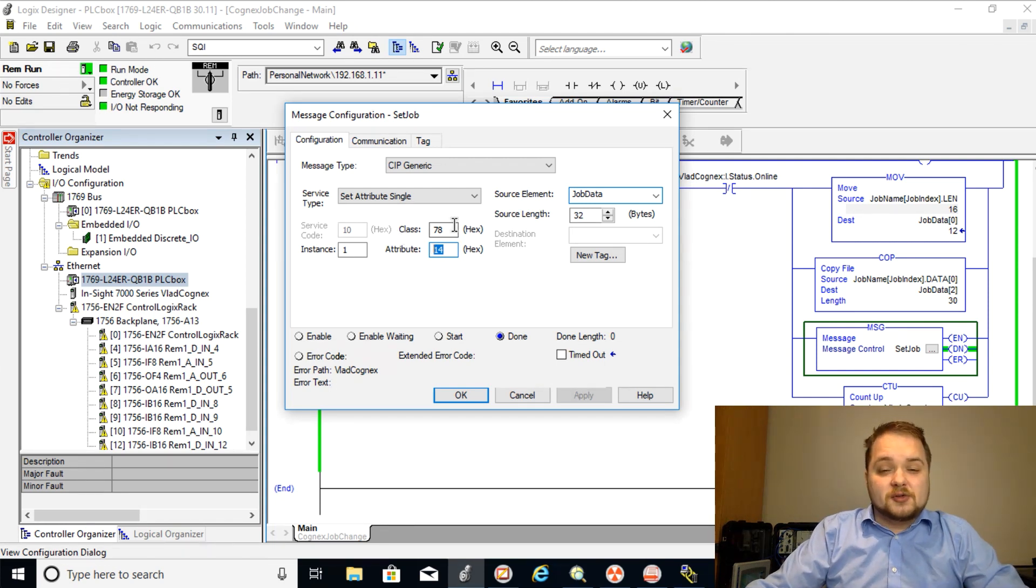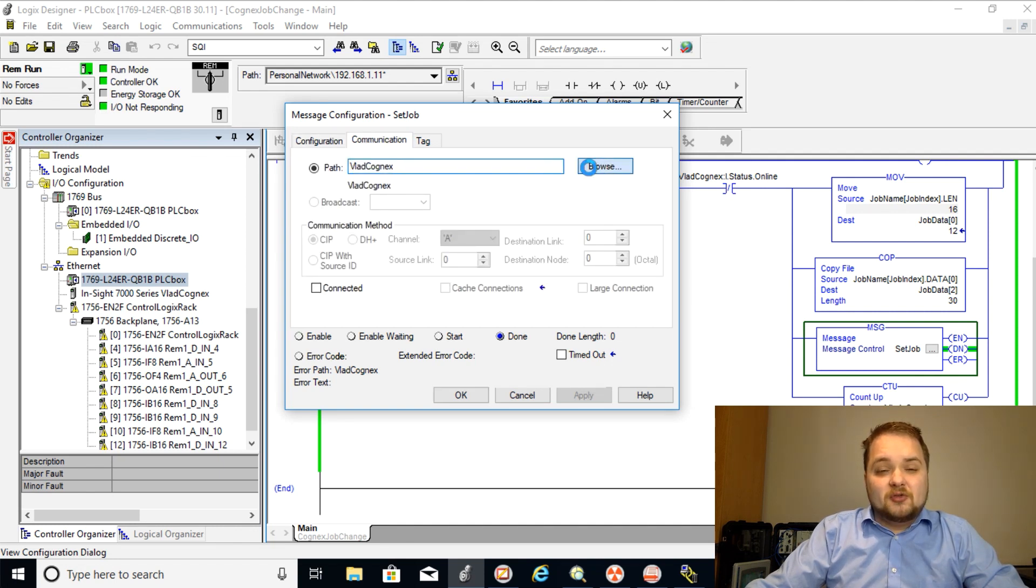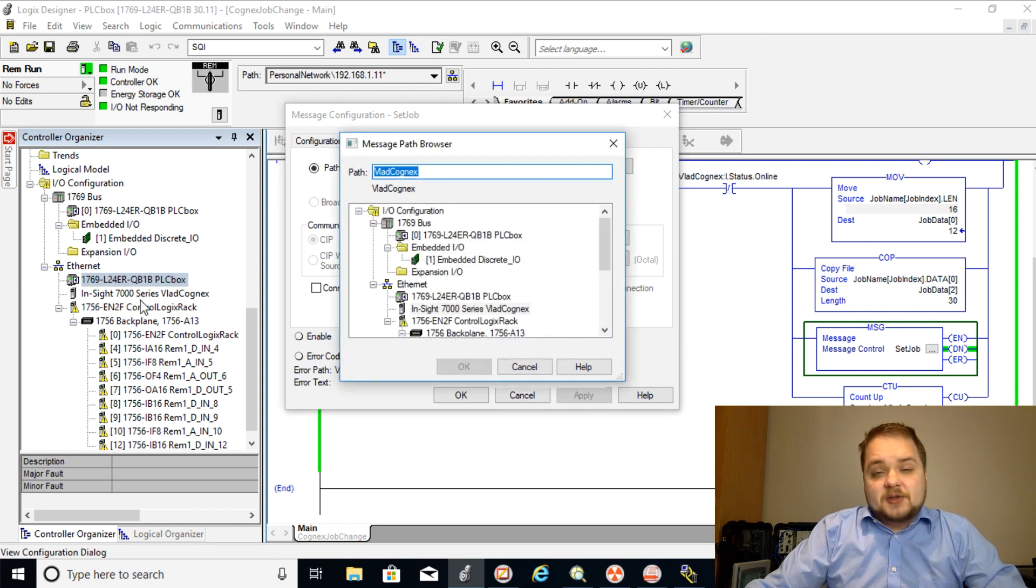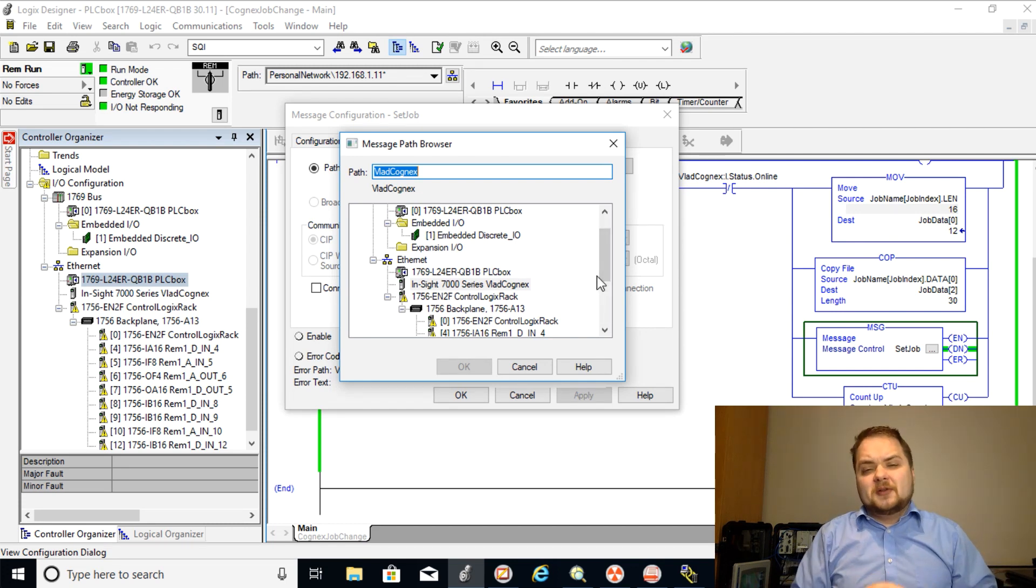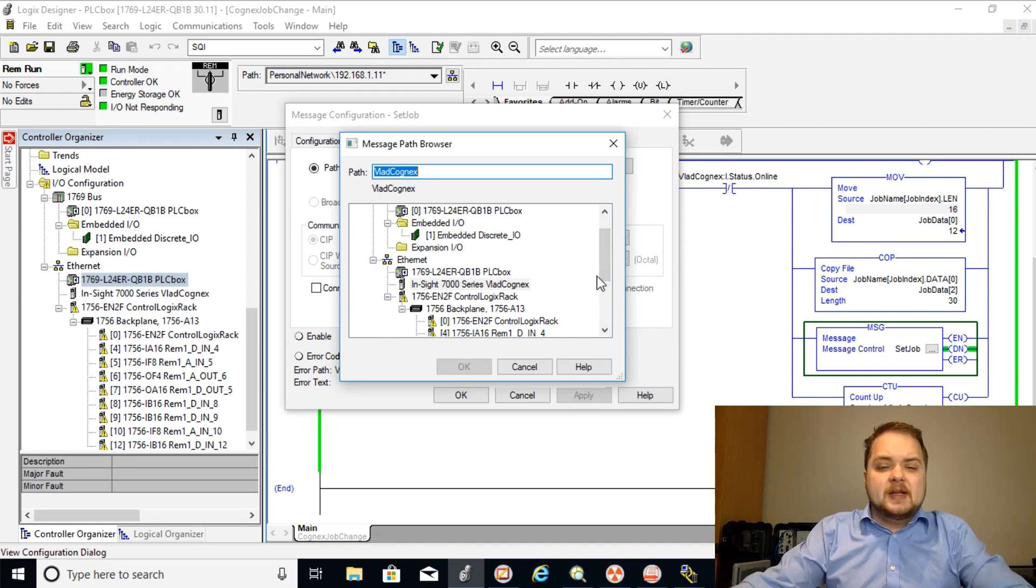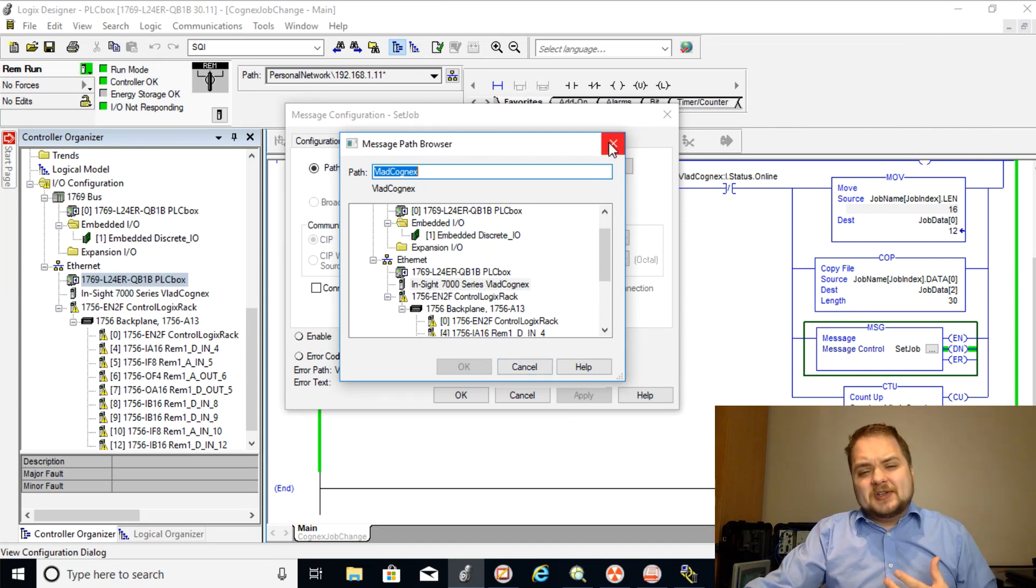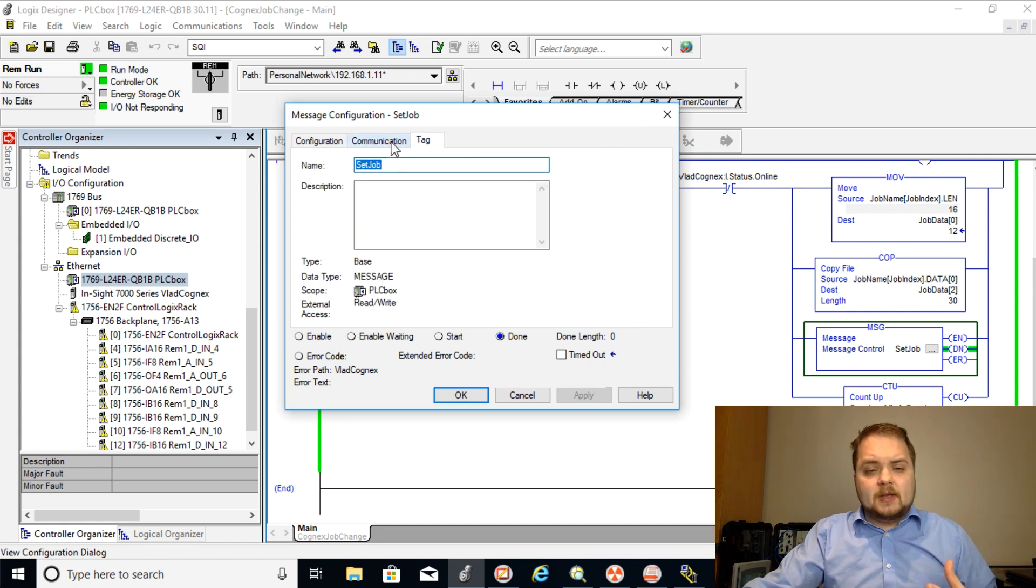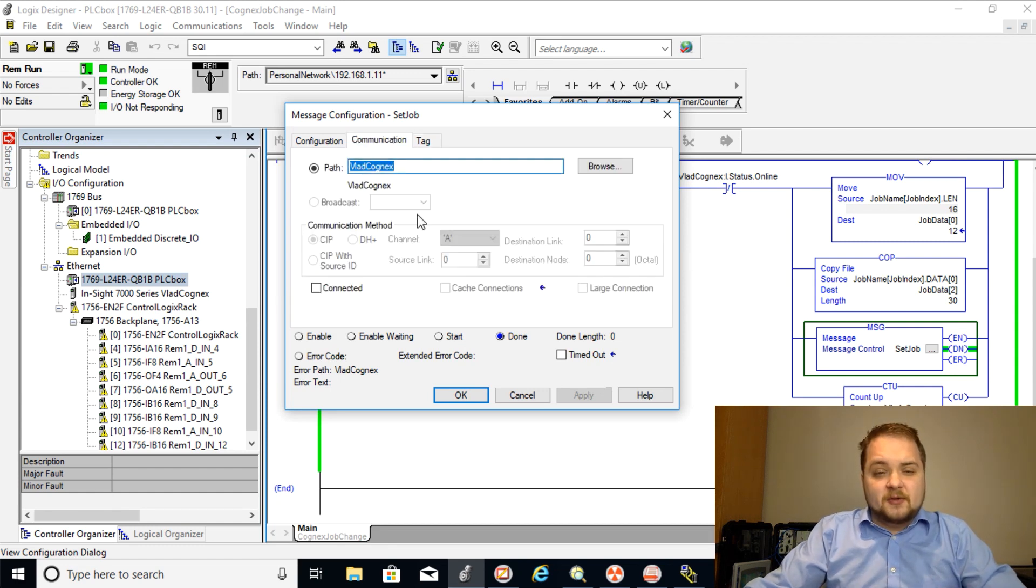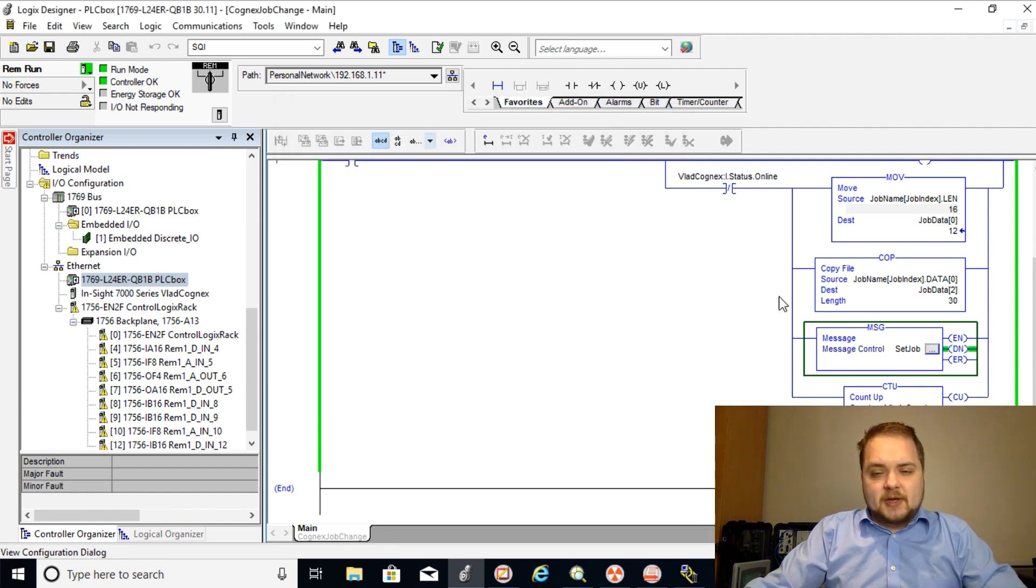Now in the communication the way you do this is essentially you need to browse to the camera and as you can see the camera is just at the immediate location in our ethernet network. Of course if you're jumping through a few maybe switches, if you're jumping through the backplane, then you still need to find your camera and make sure that the pointer for the path is in the right direction. And a tag is just the set job so that's just a generic message control instruction which is going to be specified for this purpose. We're going to hit okay.